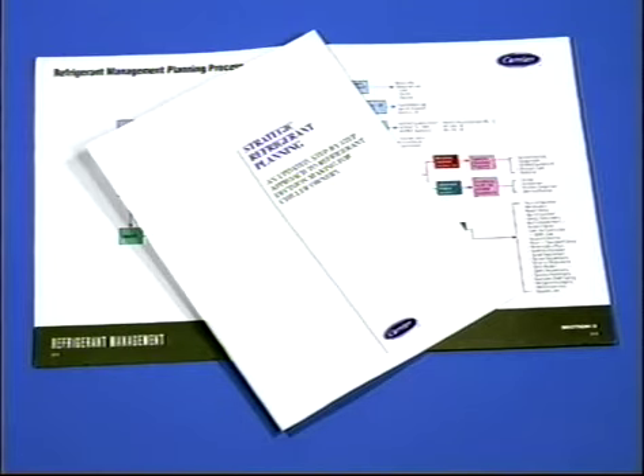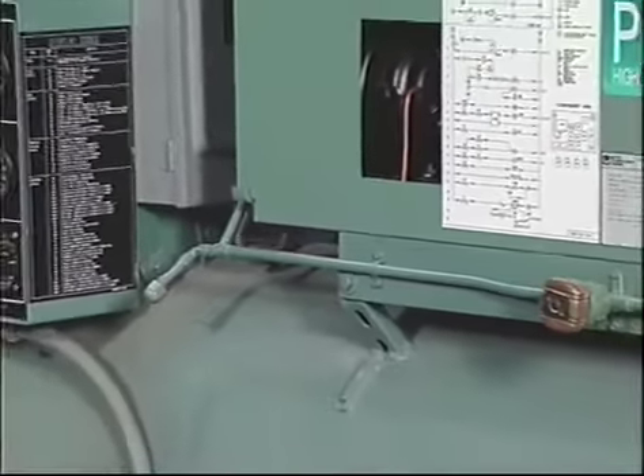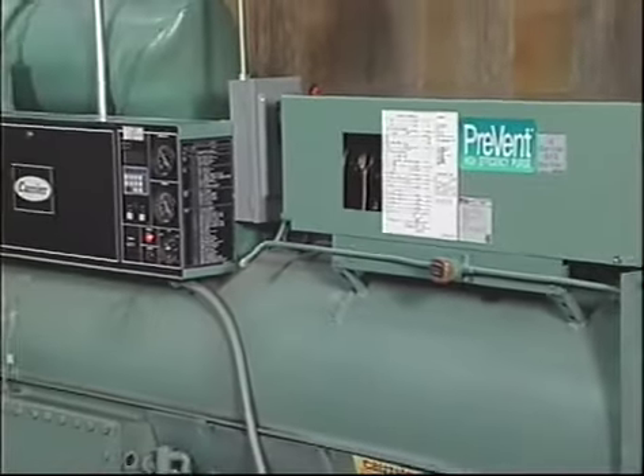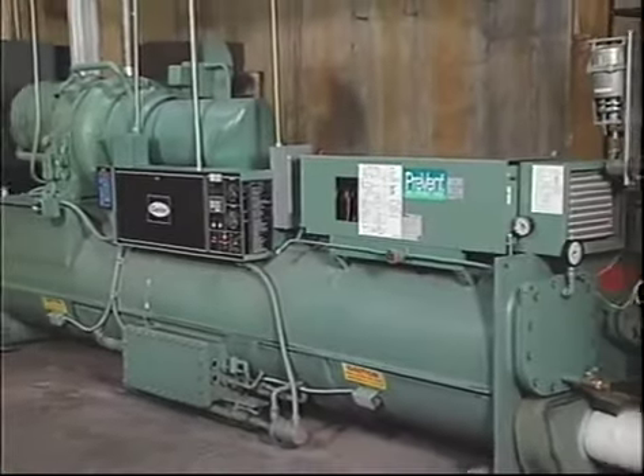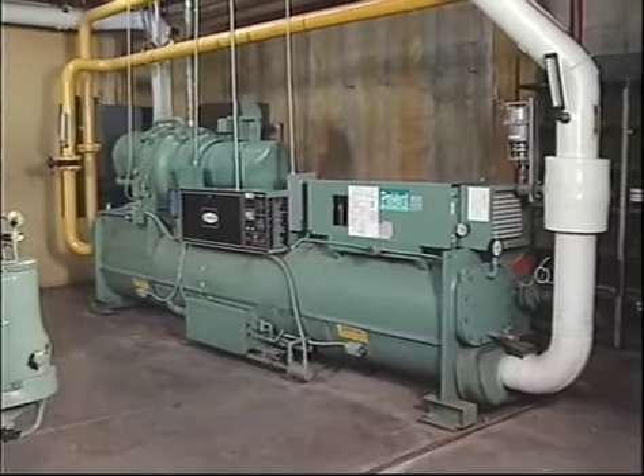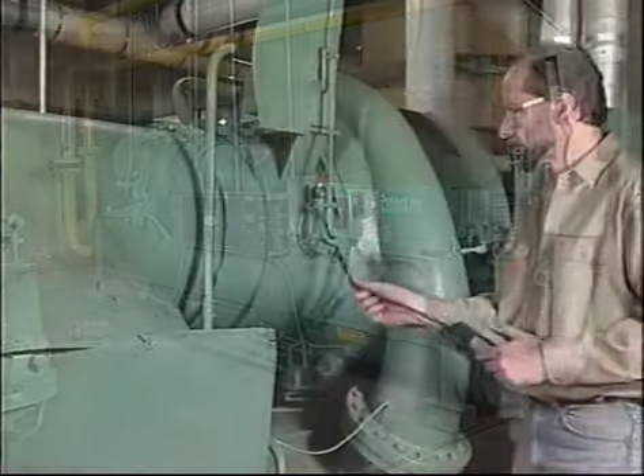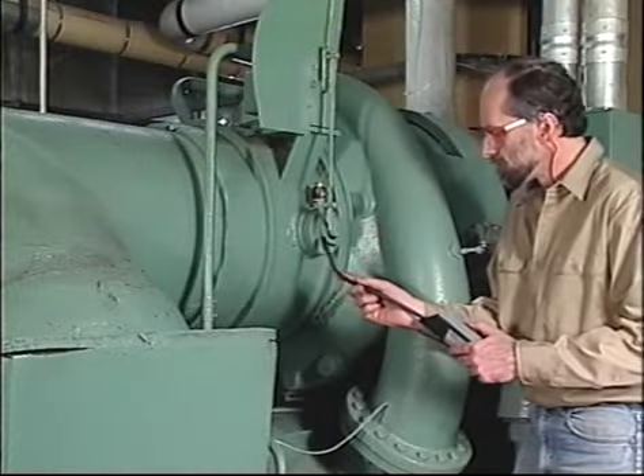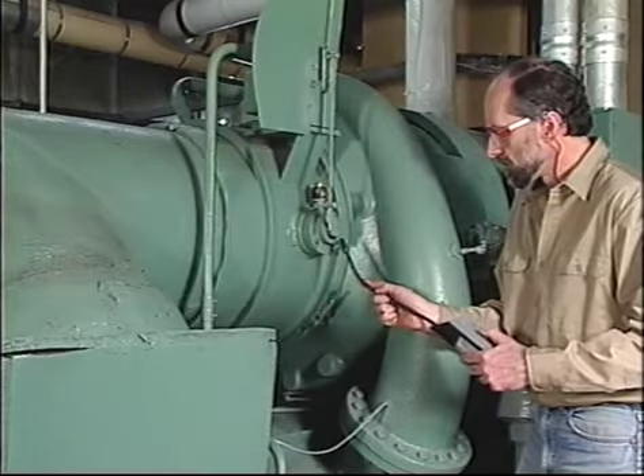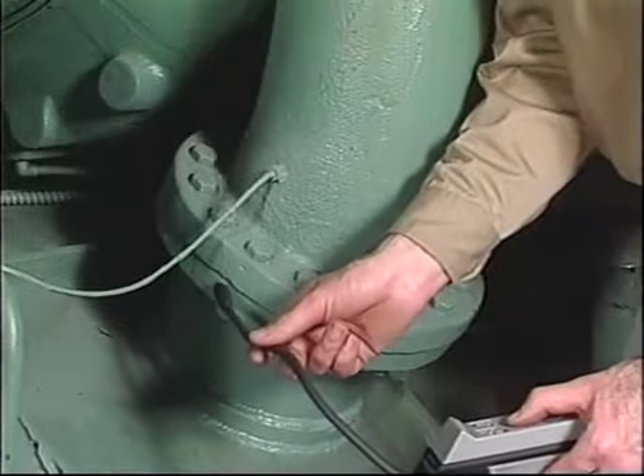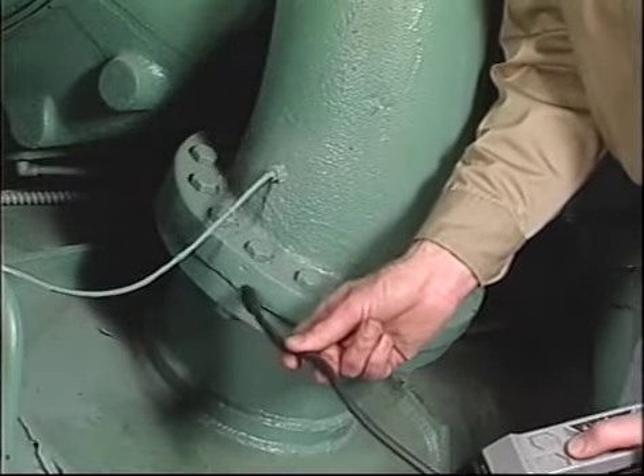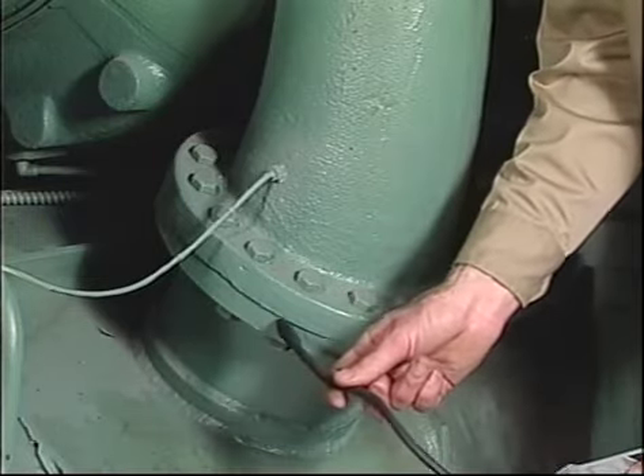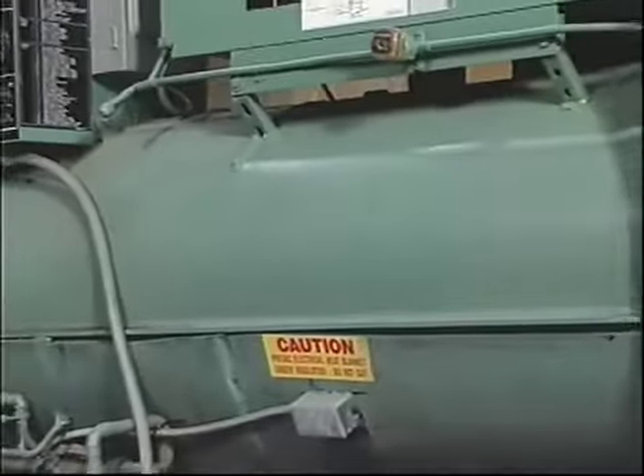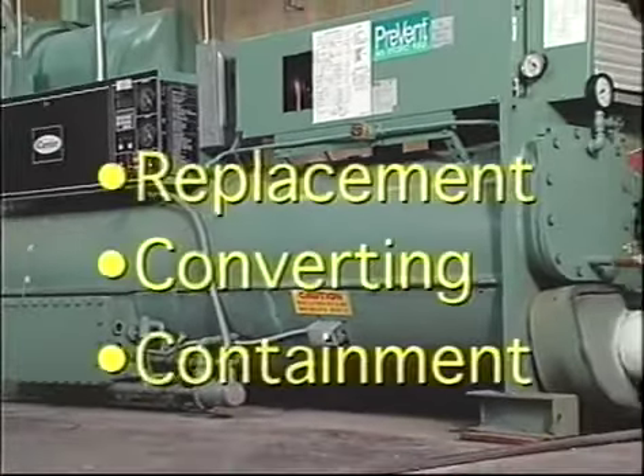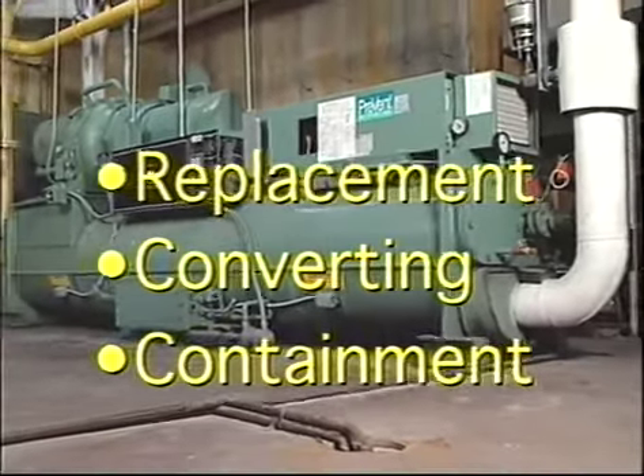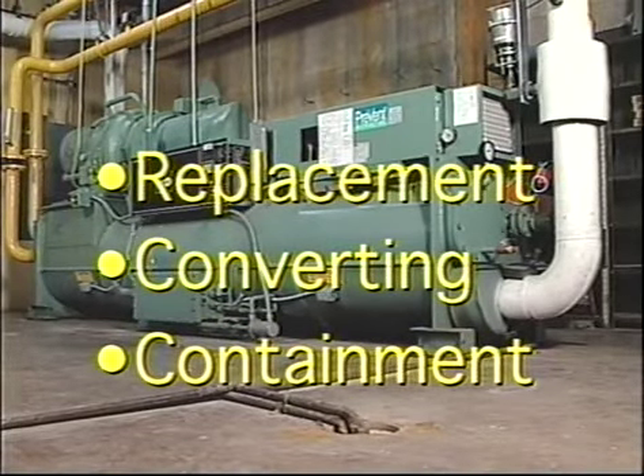of accidental emissions. For those who have low-pressure CFC chillers, the waters are considerably muddier. A continued supply of refrigerant will depend on recycling and reclaiming, and will undoubtedly become increasingly costly. Leak detection and prevention are more difficult than with a high-pressure chiller, and the penalties for emissions of CFCs are more severe. Leak prevention becomes extremely important, not only because of environmental considerations, but because of limited availability of replacement refrigerant. The owner of a low-pressure chiller ultimately faces three choices: replacing the chiller, converting the chiller to an HFC refrigerant, or containment of the CFC refrigerant.